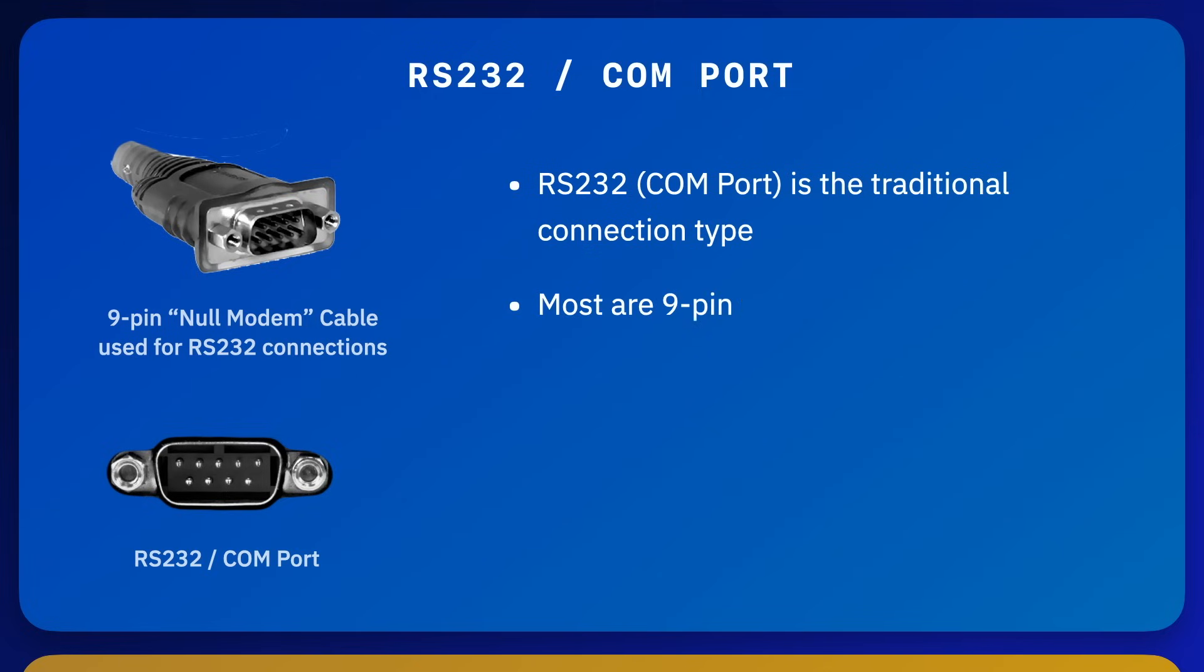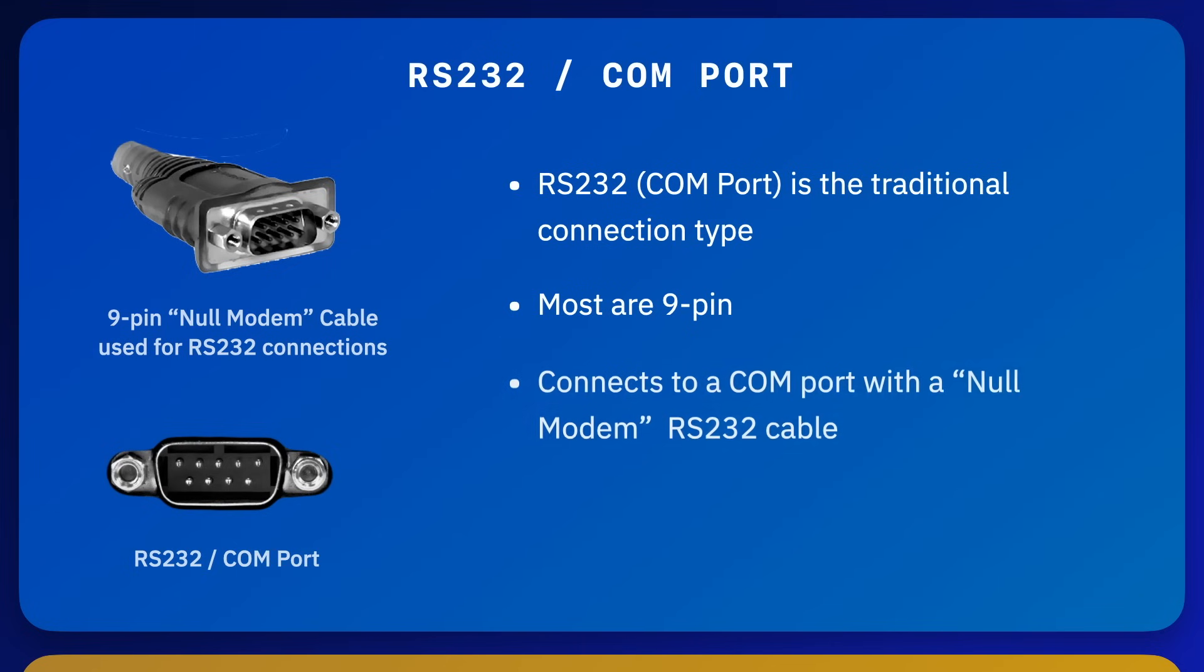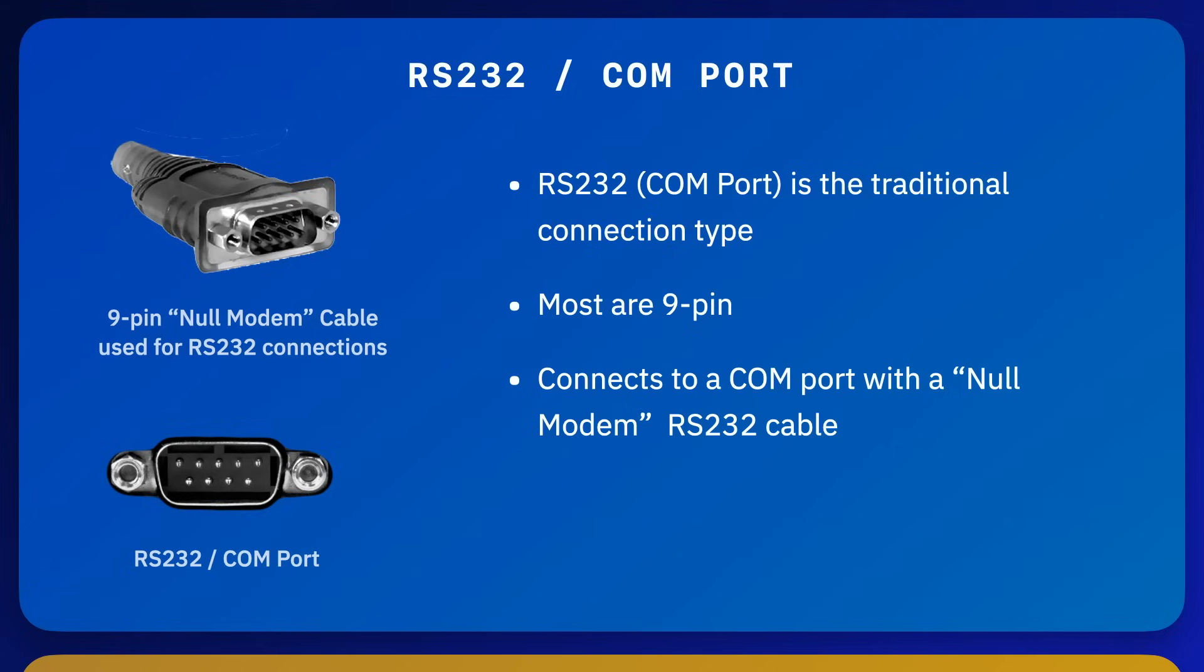To connect a balance or a scale to a COM port on a PC, you would normally use a standard null modem RS-232 cable. Null modem basically means that the transmit and receive lines in the cable are crossed.